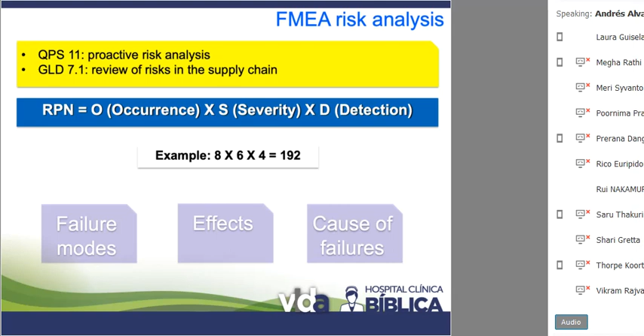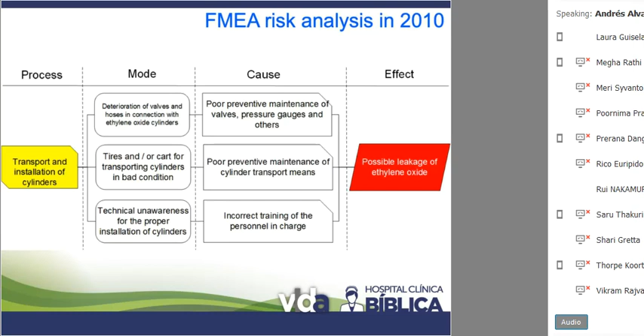This is a good example in this slide. I chose this one because the transportation and installation of cylinders, for example, was one of the most important problems related to the risk priority number. In this case, we have the process on the left side, you can see here, and then you have all the modes. For example, this mode which refers to the technical unawareness for the proper installation of the cylinders. In our case, our equipment was too old, and we had to move all the cylinders through the hospital to the area where the sterilization occurs. And then we have the causes. For example, in this case, the incorrect training of the personnel in charge could be a cause of this mode. And then the effect, the possible leakage of ethylene oxide.